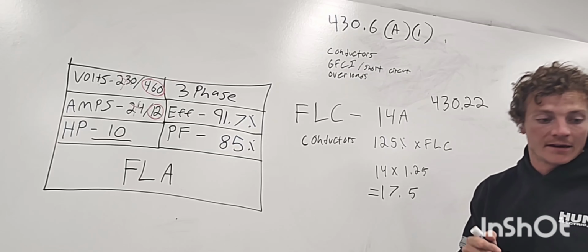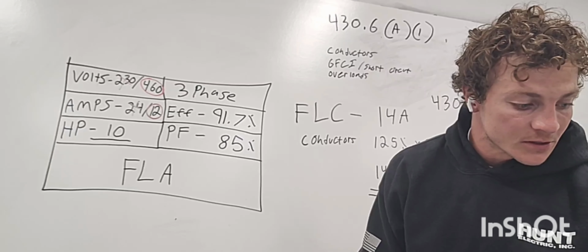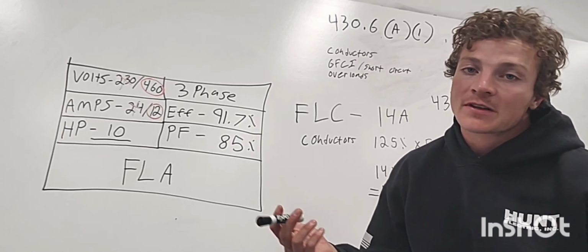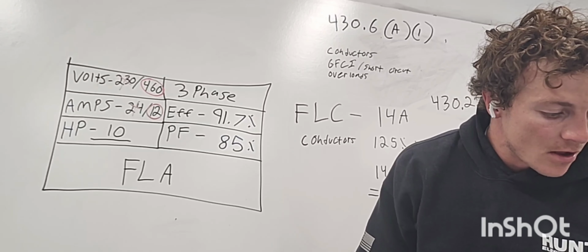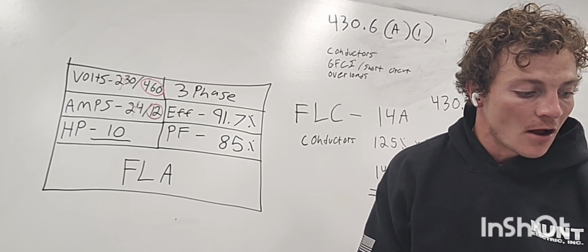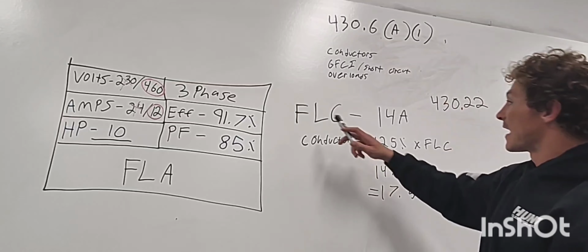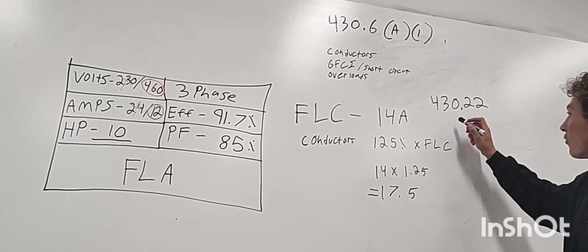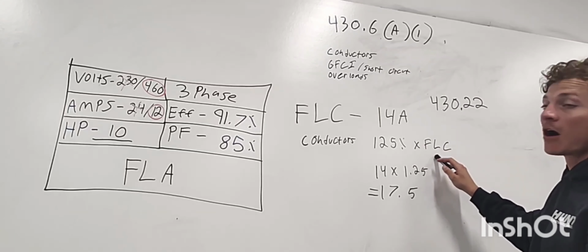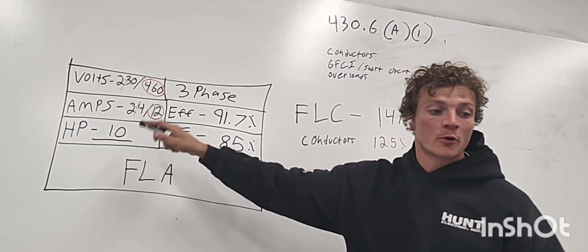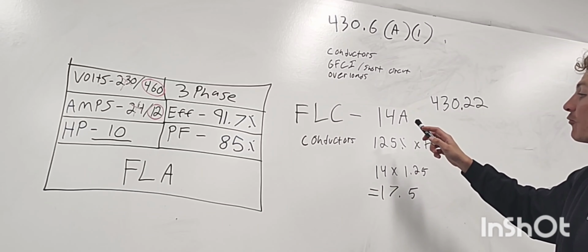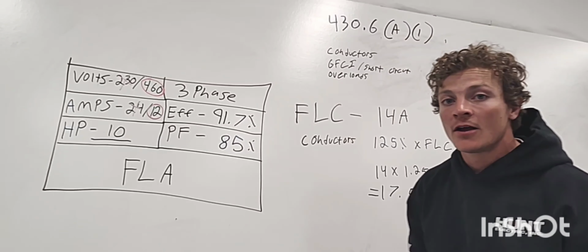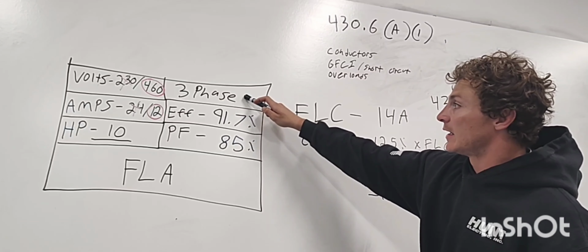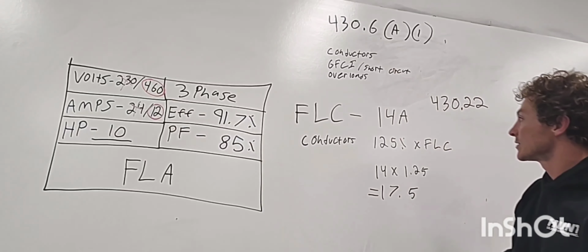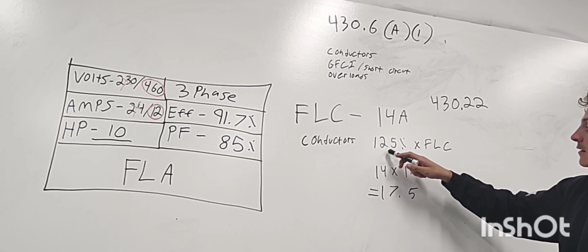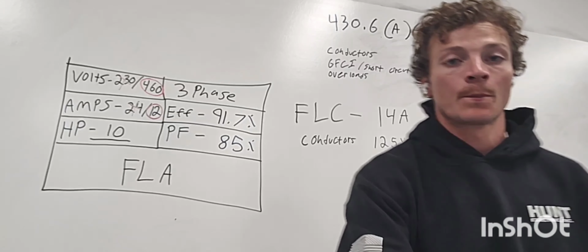Now this 125% rule is found in 430.22 of your NEC, and that says, for a single motor used in a continuous duty application, since it's a single motor, that's just what we're going to use to size it, conductors shall be not less than 125% of the full load current rating. Full load current, FLC, NEC, codebook. So 430.22 says 125% of the number that we found in the NEC. We had 10 horsepower. We went in, and in 430.250, we found that 10 horsepower on a 3-phase 460 volt motor was 14 amps times 125% equals 17.5.